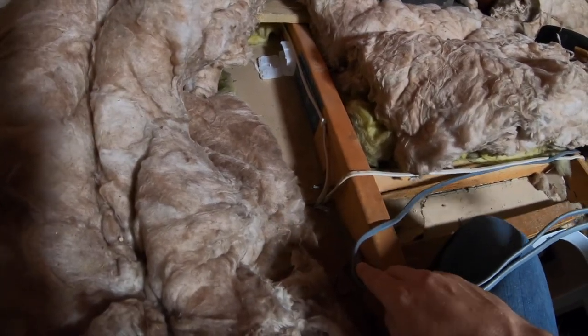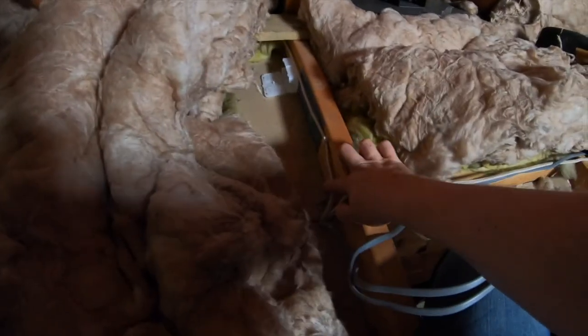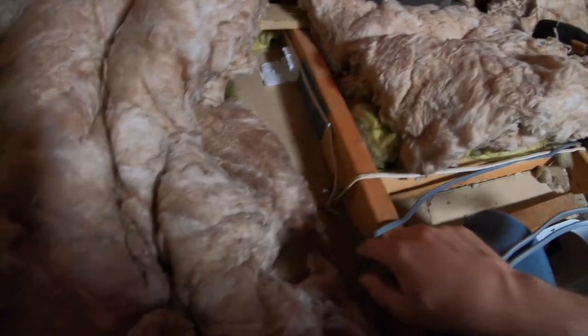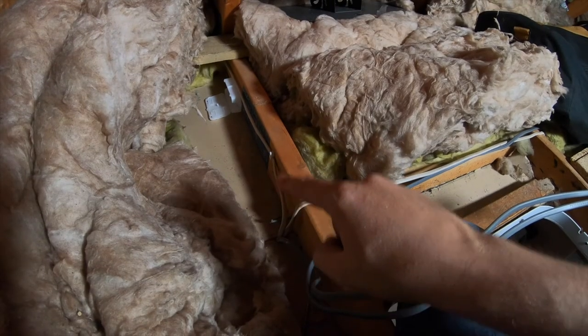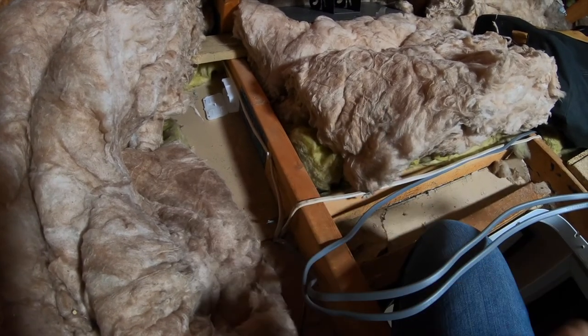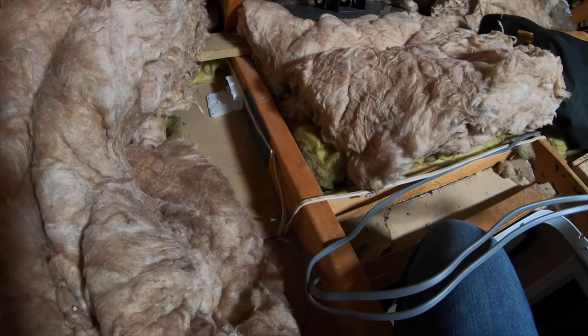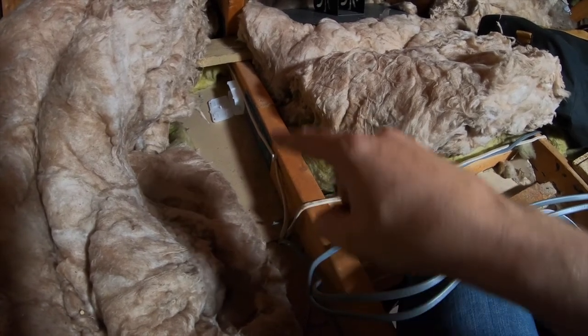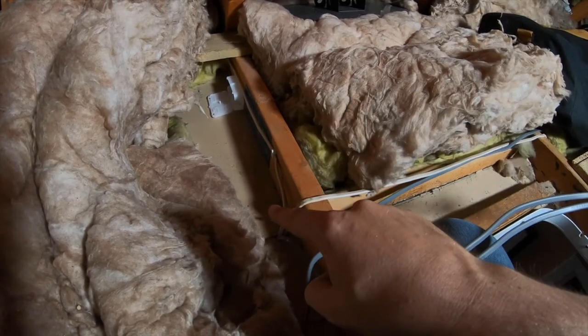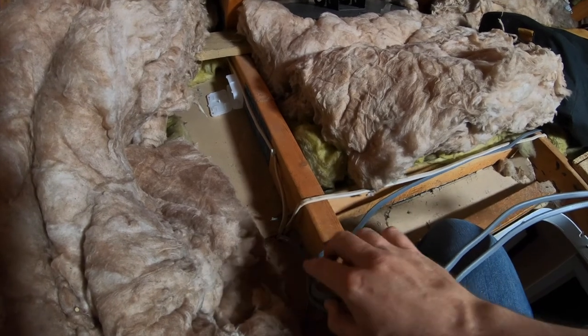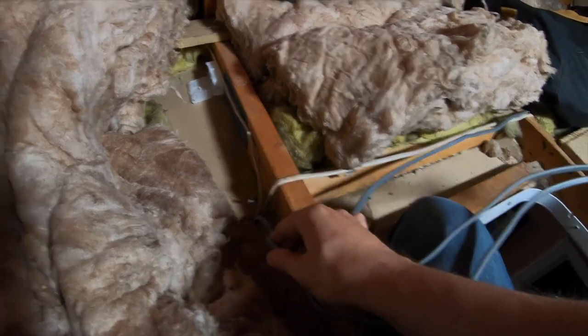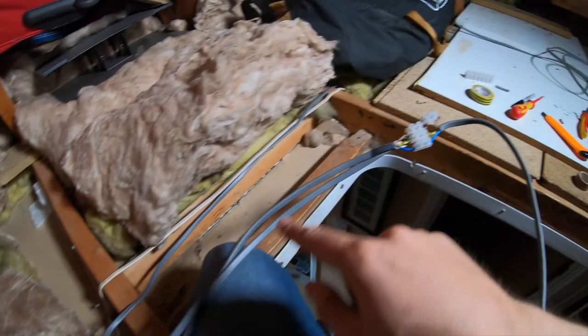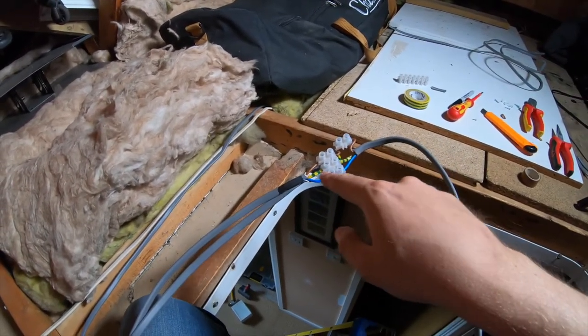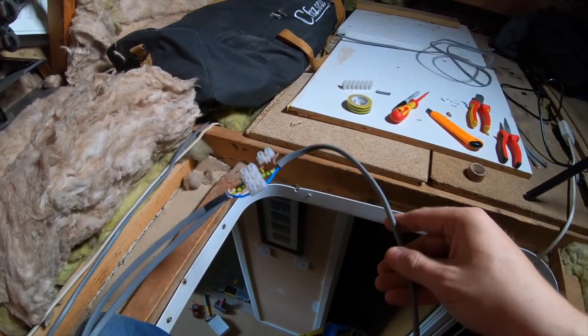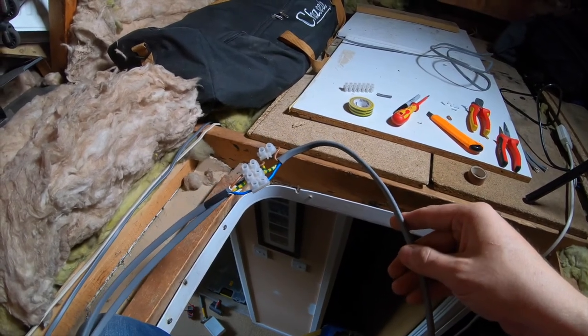And what I actually discovered is that because of the way that the circuits are run upstairs, this is actually the last light in the upstairs circuit. So most of the time you would have a feed coming in and then another feed going out, which would go to the next light. But because this is the last light in the circuit, we just have one line coming into the light and then the switch feed. So what I've done is I've then added another line coming out again, and that then goes to this connector block, which basically connects to this cable, which is going to be what I'm going to use to connect the lights.